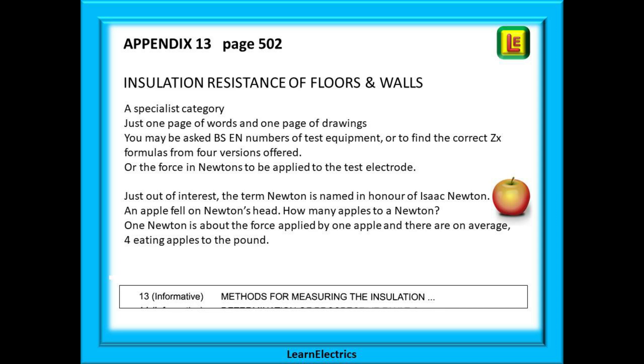Measuring the insulation resistance of floors and walls is the subject of appendix 13. In some regs books the full title has been chopped off — all it says is '13 methods for measuring the insulation.' If I were you I would add 'resistance impedance of floors and walls' to your book on page 3. It is a specialist subject with only one page of words and one page of drawings. Out of interest, some people ask what is the force of 750 newtons shown at the bottom of page 502. In a very unscientific way: one newton is about the same force as an eating apple in your hand at sea level, so 750 newtons is the same as 750 apples — about 85 kilograms of force, or the same as an average male standing on your hand.